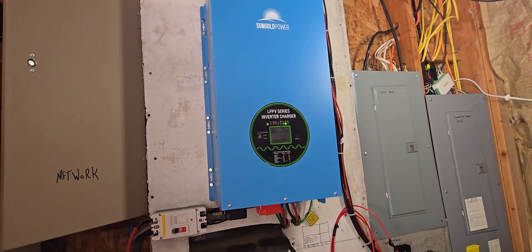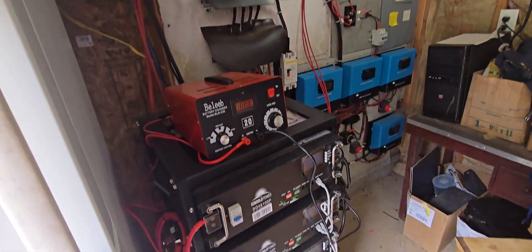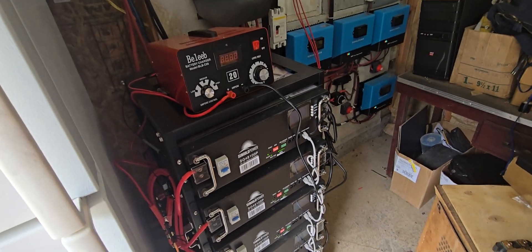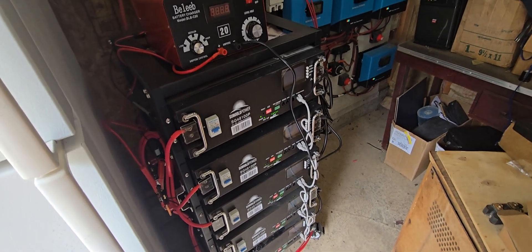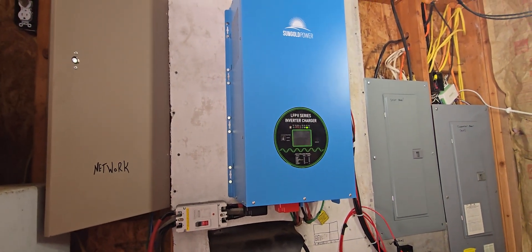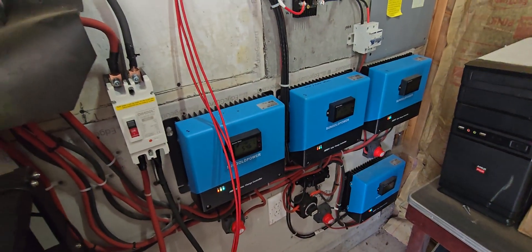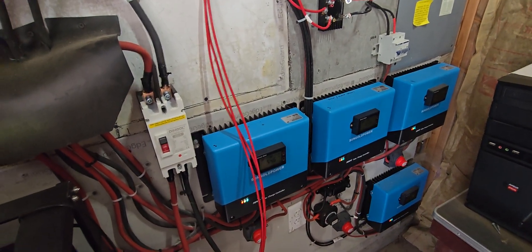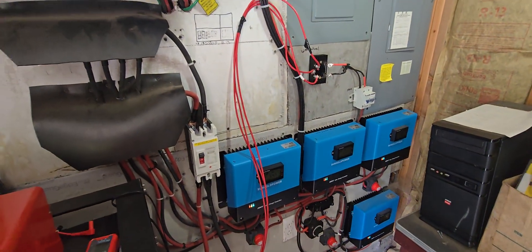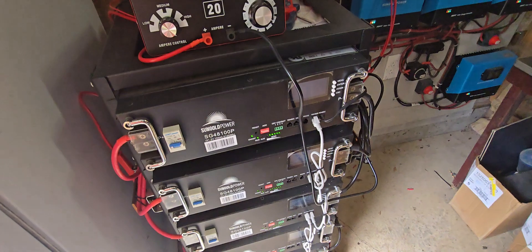A hybrid inverter runs off of the battery bank right here — that's five 100 amp-hour batteries, so 500 amp-hour batteries all bonded together. The inverter runs off of those. These are charge controllers, and they limit the amount of power fed to the batteries once the batteries are full. Once they're full, those regulate the DC power coming from the solar panels and how much it pushes out to the batteries.